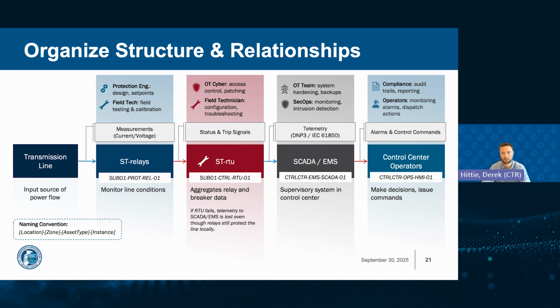And then we get to the remote terminal unit, the RTU. It depends on relays, breakers, and sensors feeding it information. It aggregates all of that status and trip data and then transmits it upstream, typically over protocols like DNP3 or IEC 61850 to the supervisory systems. Now, at the SCADA and energy management system layer, these supervisory systems depend on the RTUs to provide a steady stream of telemetry and alarms. That data feeds the operator displays, triggers alarms, updates logs, and provides a control path back down to the substations. And finally, we land in the control center operations. Operators depend on the SCADA and EMS system to maintain situational awareness.